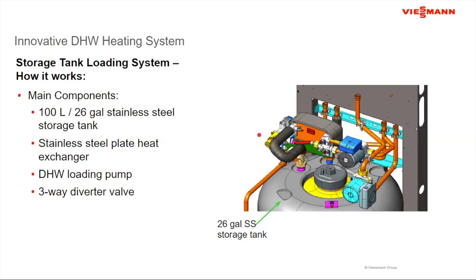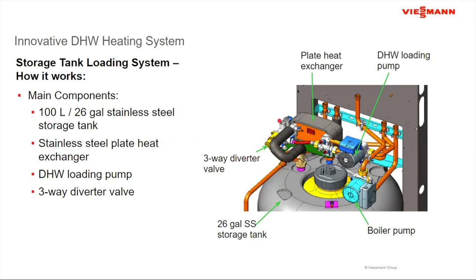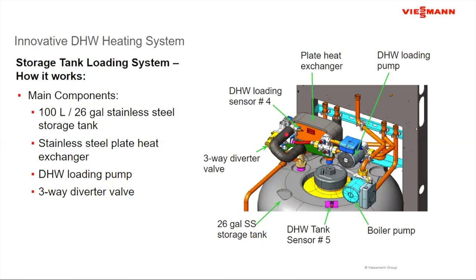Domestic hot water is produced like in a combi boiler, through a plate heat exchanger, utilizing a domestic hot water loading pump and a boiler pump, and also a three-way diverting valve to shift between space heating and domestic hot water heating. Like an indirect, there is a tank sensor. Like a combi boiler, there is a domestic hot water loading sensor. The tank sensor starts the process off. The loading sensor modulates and maintains water temperature.